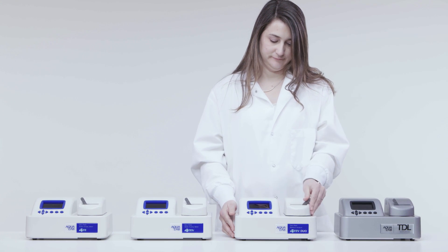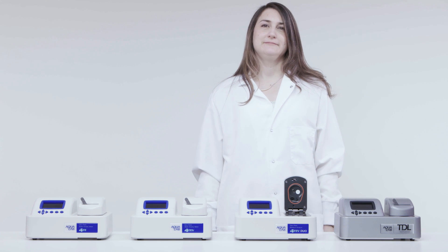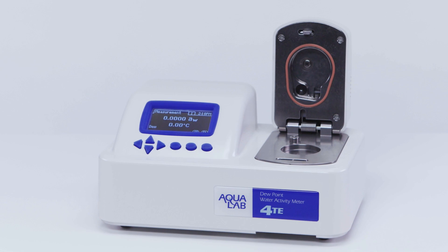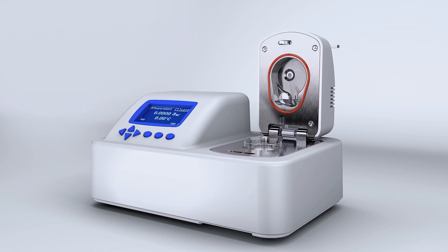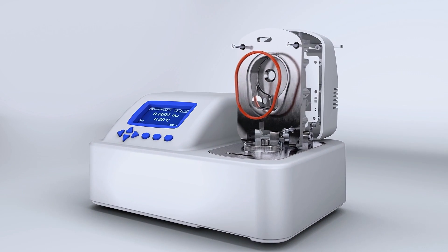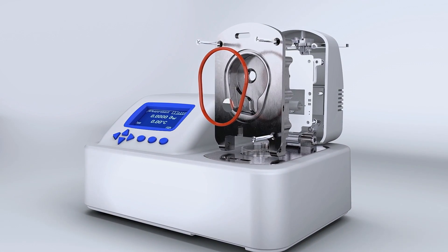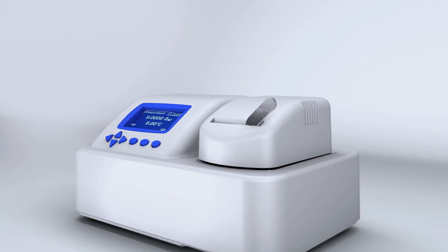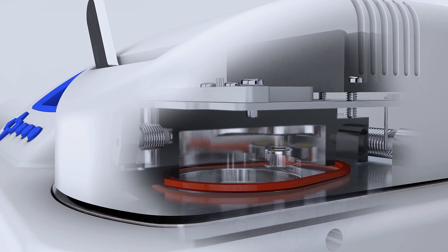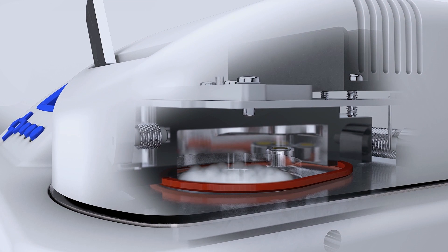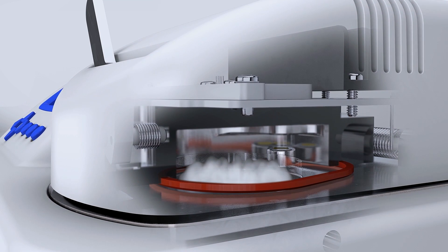There are four different types of Aqualab water activity meters. The one we're using in this video is the Aqualab 4TE. It uses the chilled mirror dew point method to measure water activity. When a sample is put into the chamber and the block is sealed, it comes to vapor equilibrium. Water molecules enter the air above the sample, and then the mirror is chilled until dew forms.